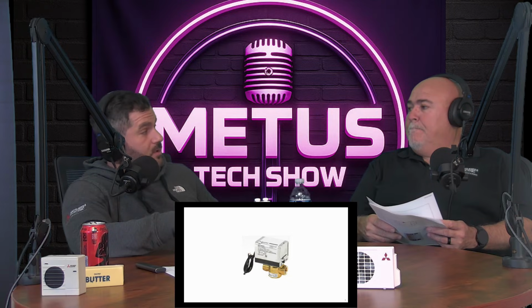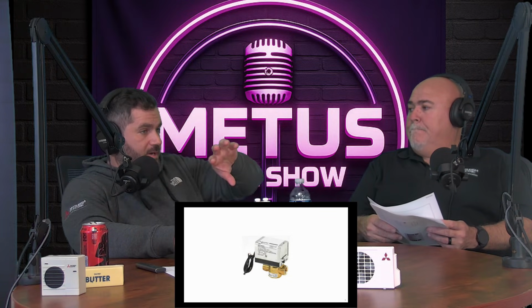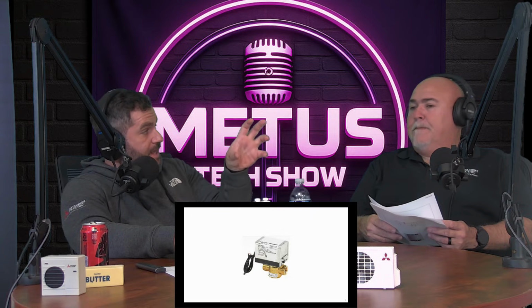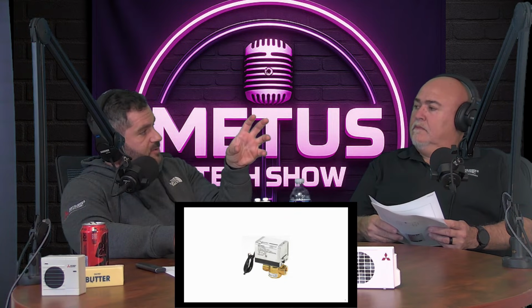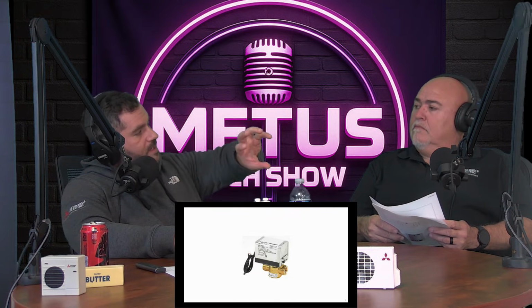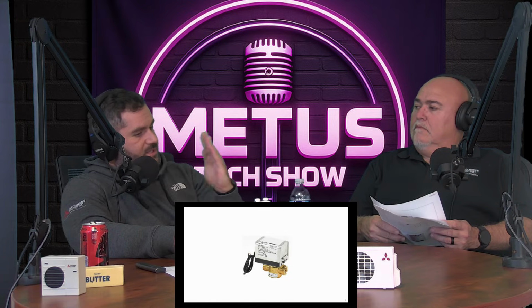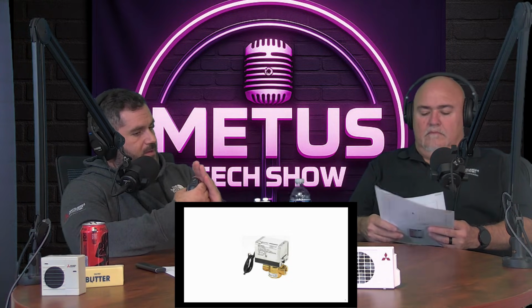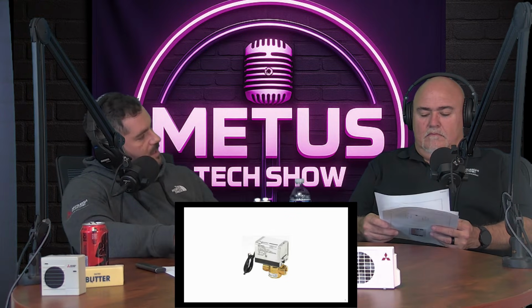And inside there is just a motor. And so there's a spring in there. It will spring close. There's always a spring fighting it to close. And then when it gets that 24-volt signal, the motor will override that spring and open up. It's a little like a flapper in there. It's like a hard plastic flapper that will sit nice and tight against the body or the inside of that valve to prevent water flow. And the motor will swing it open when it gets energized.